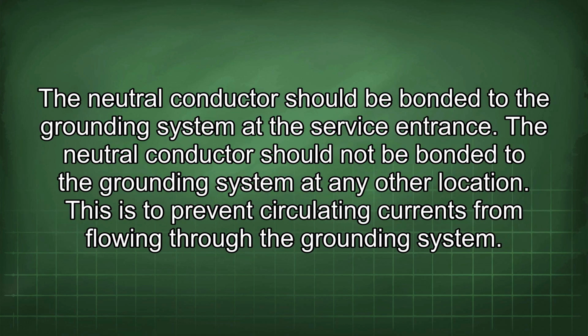The neutral conductor should be bonded to the grounding system at the service entrance. The neutral conductor should not be bonded to the grounding system at any other location. This is to prevent circulating currents from flowing through the grounding system.